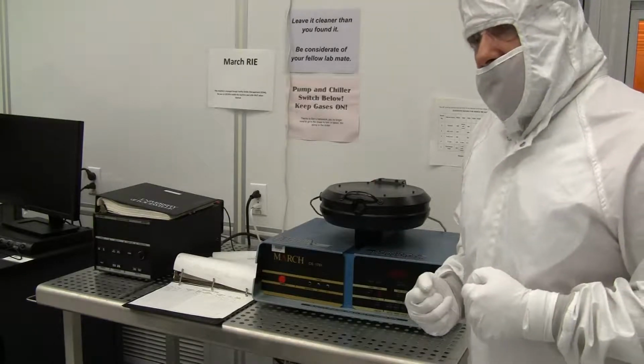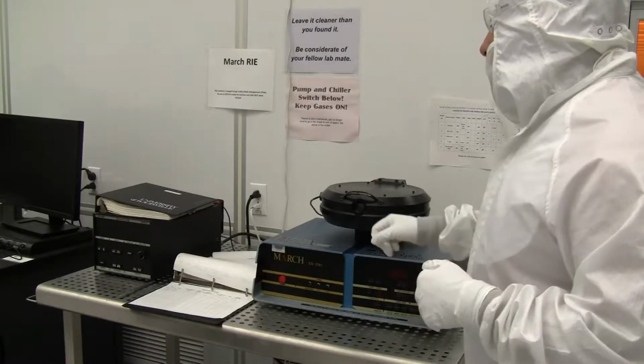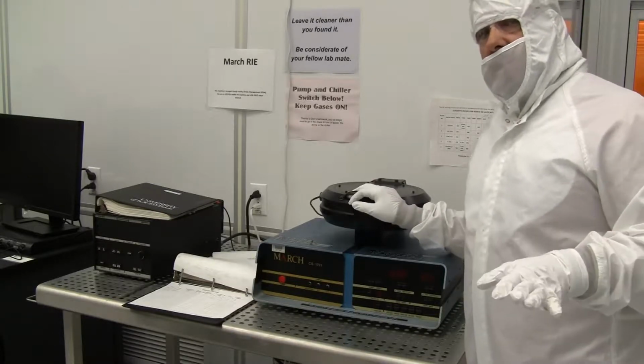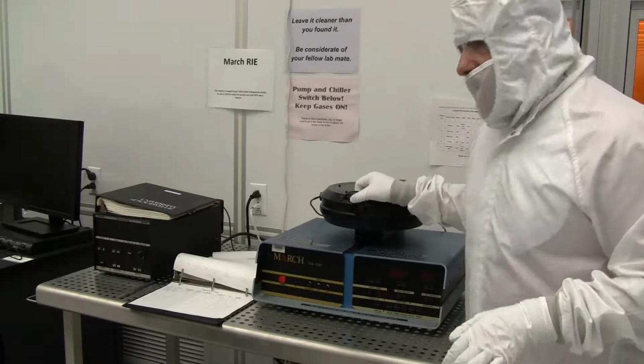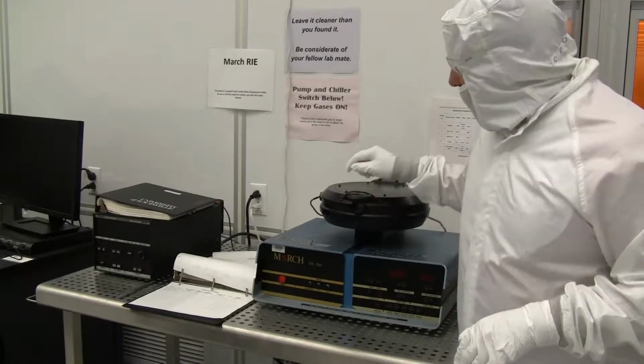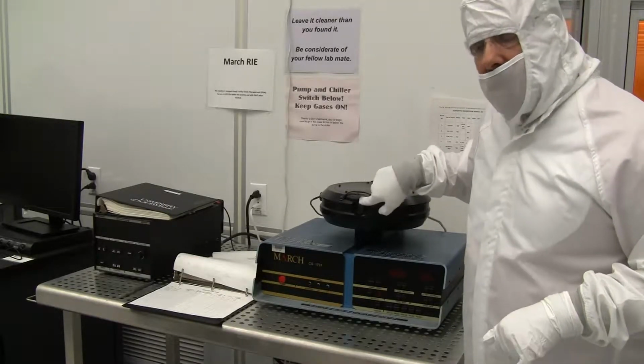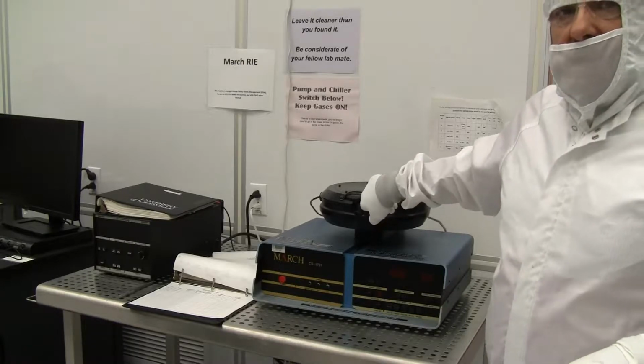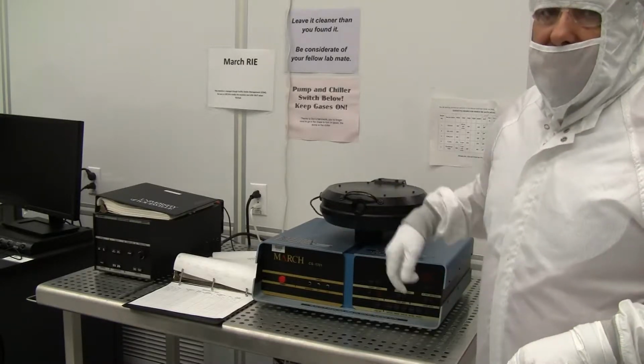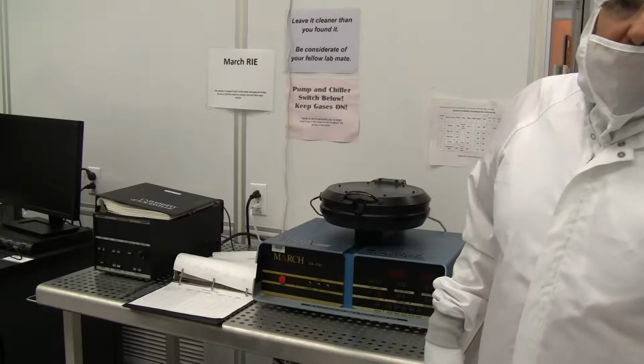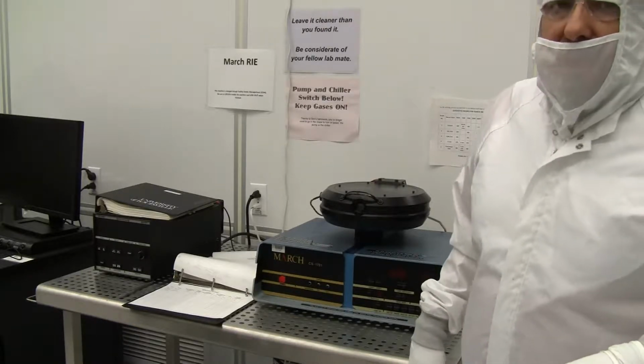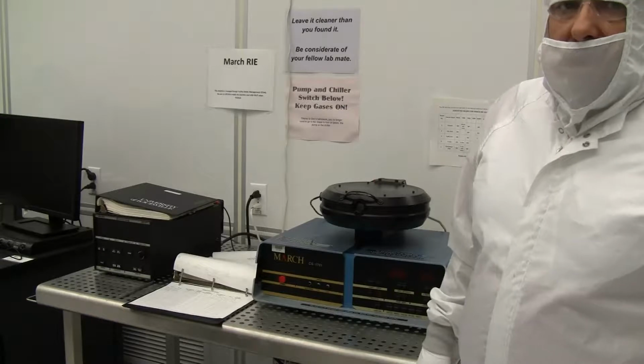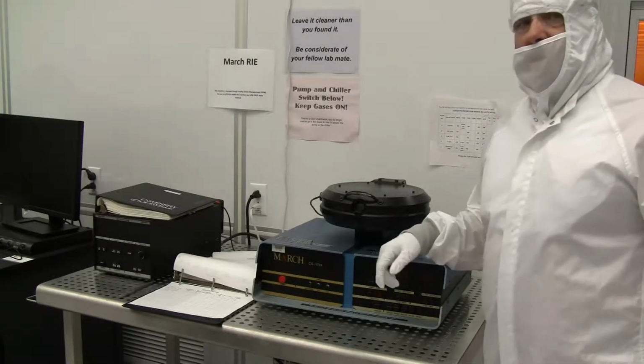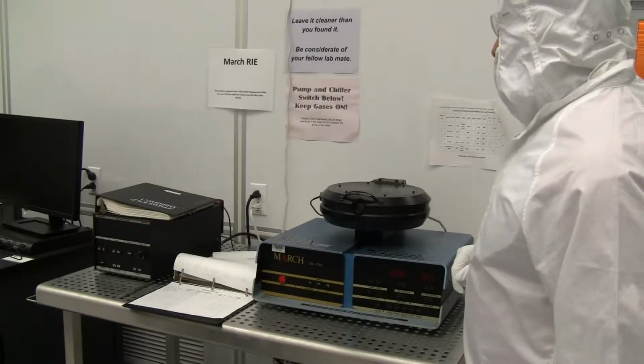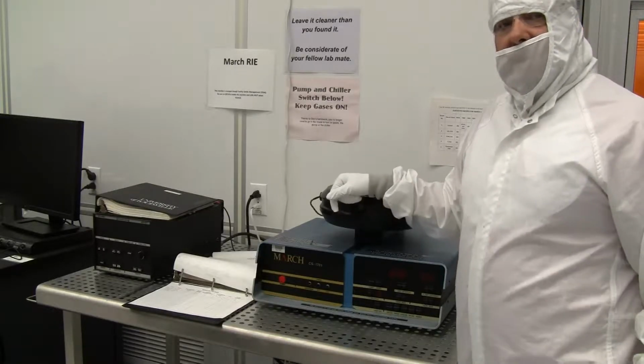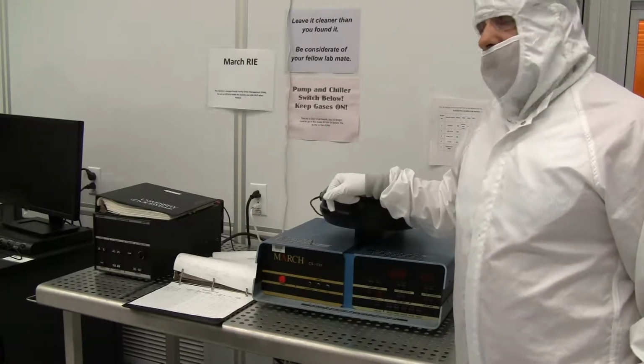Today I'm doing some maintenance on this guy. Apparently one of the mass flow controllers' calibration has wandered, and it sounds like there's a good chance that one of the O-rings, specifically the O-ring in this little window here in the chamber, may have gone south. It's consumable since it's running oxygen plasmas through there. Oxygen plasmas are, of course, great at etching carbon atoms, turning them into CO2. I'm going to do some diagnostics on this, and I'll show you a little bit about how this works.